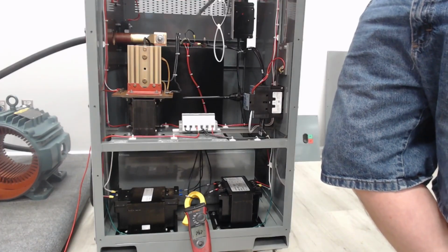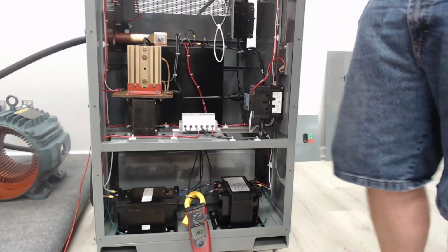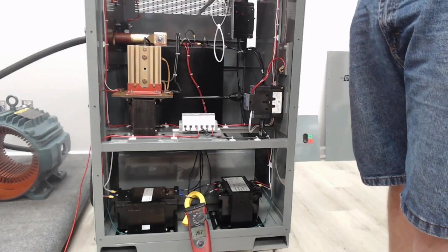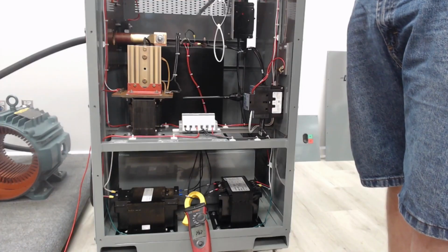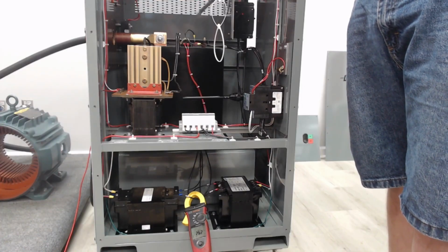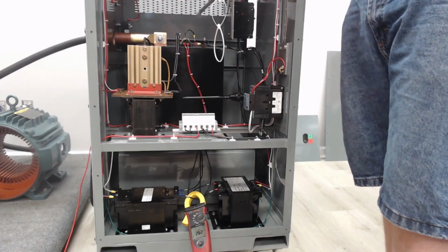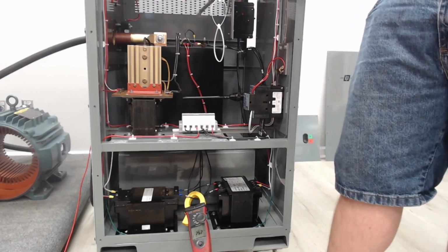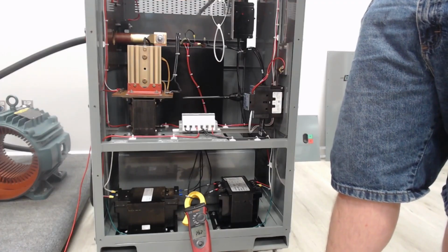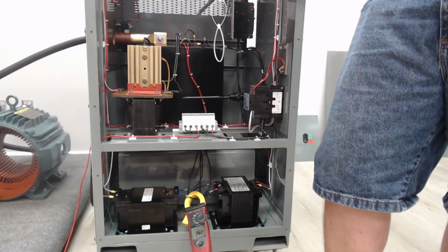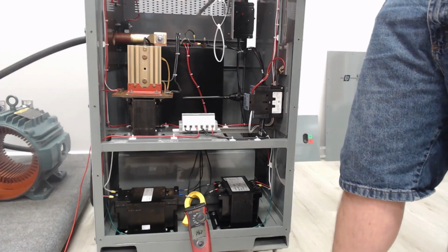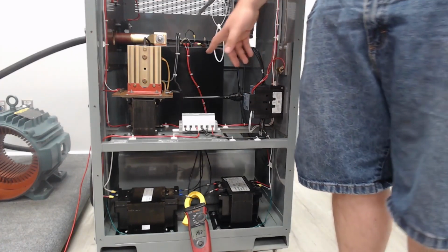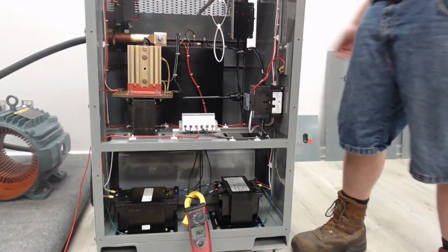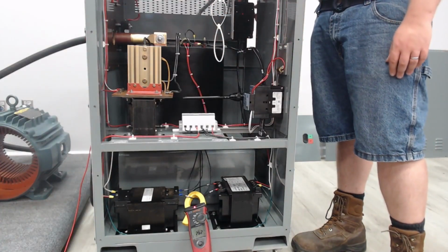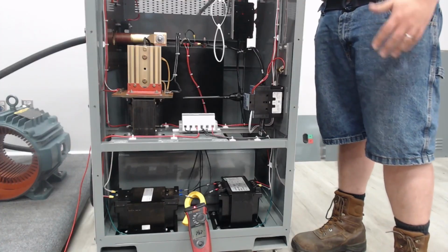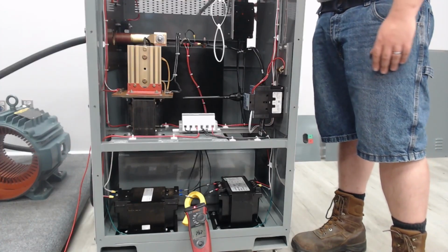You can also do this the same way. Hook it up to voltage, use alligator clips to hook onto that transformer, and do your min-max function on the voltage. You're just trying to make sure that your voltage is not dropping below that 460 or whatever your nominal is. If it is, then obviously you're not supplying enough power, and with that inrush heavy draw, you're getting way too much current to trip that breaker. Now, obviously, we exceeded that fuse, but it's a time delay, so it doesn't matter. I can still turn it on. Unit will work. You can't hear the hum, but it's definitely still working. We have no issues at this moment.